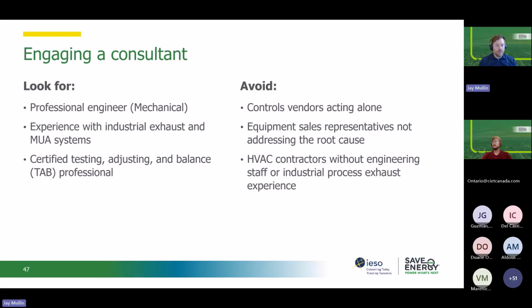You want to make sure that you are getting a consultant that has experience with industrial systems. So negative pressure in these facilities is usually caused by unaccounted for or unnecessary exhaust, and not necessarily that HVAC system imbalance that we were talking about before. So you want to make sure that the consultant does have experience with industrial process exhaust systems, because that's going to play a really big role in it, or most likely. You can look for certified professionals. So testing, adjusting, balancing, TAB professionals. They're very well equipped to measure actual airflow, perform pressure mapping, that mass balance across different areas. There's different credentials like AABC, NEBB, TABB that you can look for.